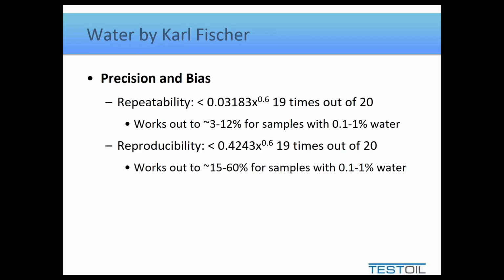So when it comes to water content, we probably shouldn't nitpick very small changes. The point is, you have water in your system. Water is never a good thing. Corrective actions need to be taken. You can't really worry too much about the decimal points on the water value.